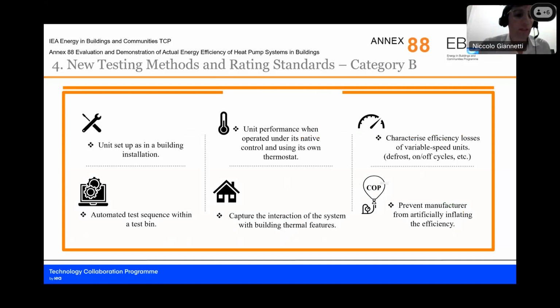So category B standards, or new testing methods that are being developed at present to overcome the limitations of previous standards, need to focus on these additional points that are challenges, but also opportunities for more valuable information extracted by each test. First, the unit should be set up in the same way as it is installed in a building. So no proprietary control is needed. The thermostat is operated in the same way as it is operated in a building. And this comes to point 2, where the unit is operated according to its native control and follows the response according to the temperature or humidity, in case there is a humidity sensor in its own thermostat.